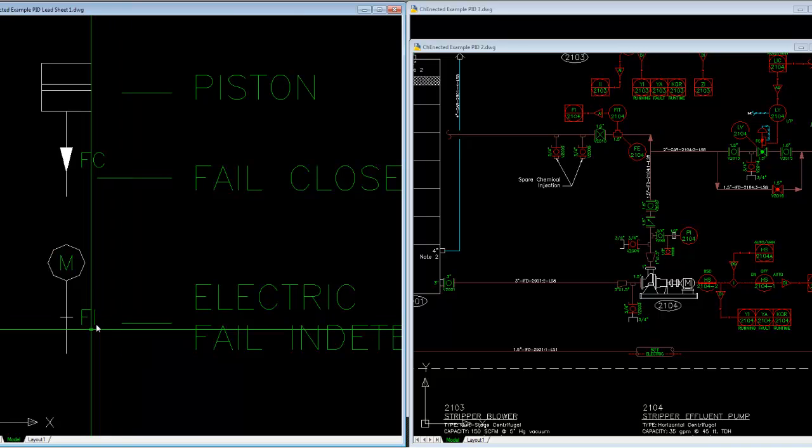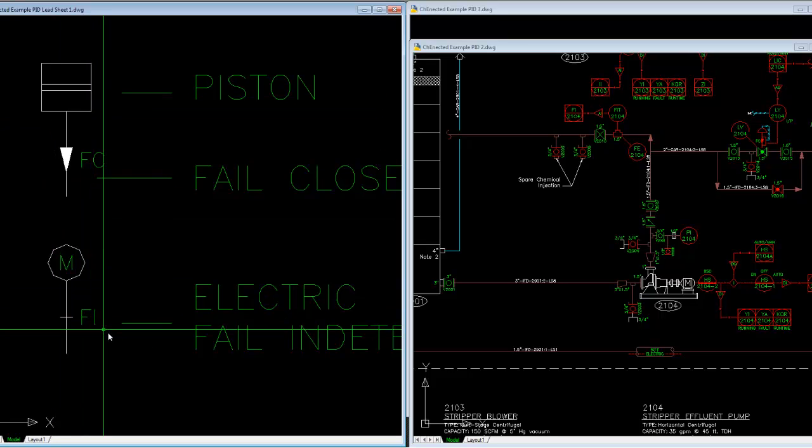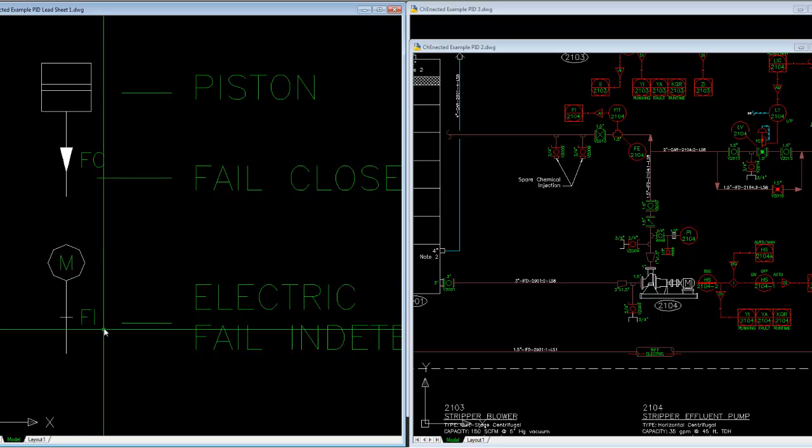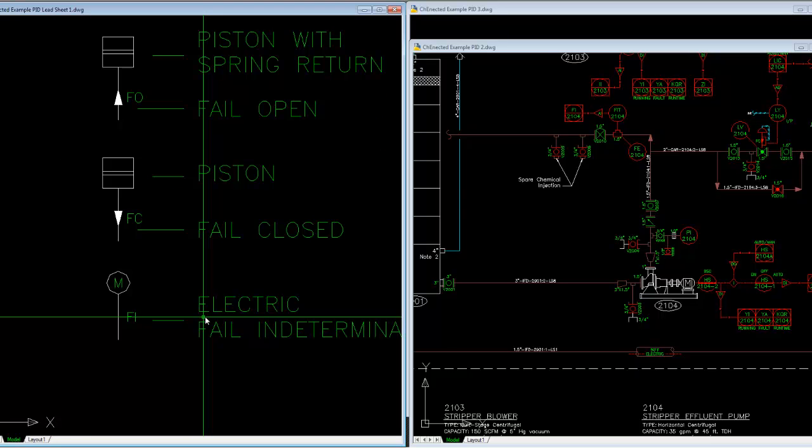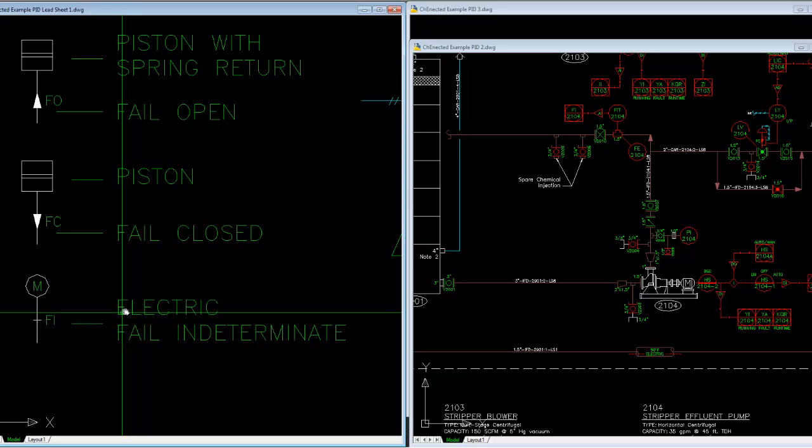A lot of times motor actuated valves don't have a clear fail state because there's nothing that's driving them to some fail state, like a spring would drive a piston, although you can get them with that. A lot of times when they fail, it's unknown where they're failing or where they're going to.